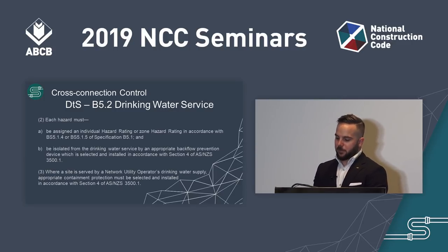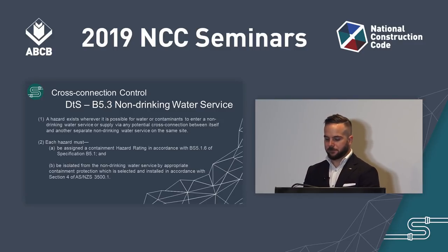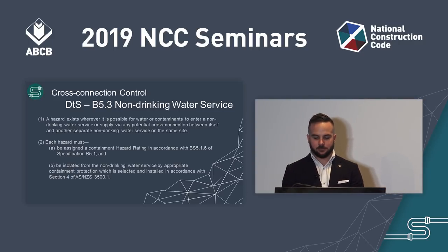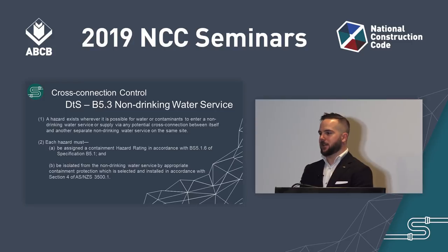B5.3 covers cross-connection control of non-drinking water services. This provision states that a hazard exists wherever it is possible for water or contaminants to enter the non-drinking water supply or service via any potential cross-connection between itself and another separate non-drinking water service on the same site. A separate non-drinking water service means one that draws water from a different source — for example, a site connected to both recycled water and rainwater. Each hazard must be assigned a containment hazard rating in accordance with Specification B5.1, and be isolated from the non-drinking water service by appropriate means of protection selected and installed in accordance with AS/NZS 3500 Part 1.